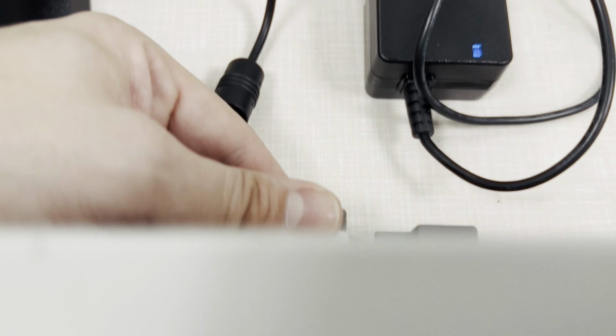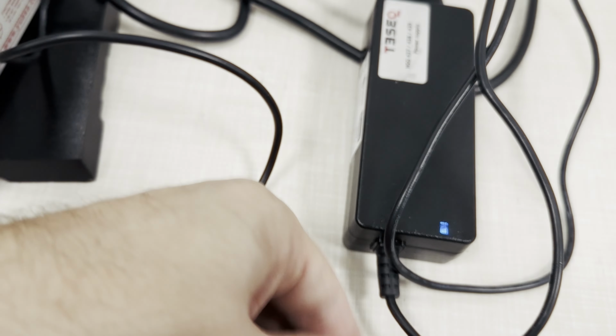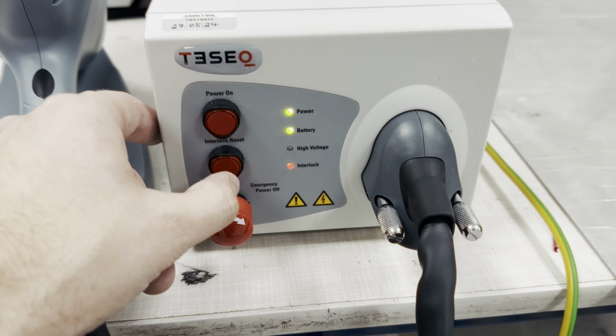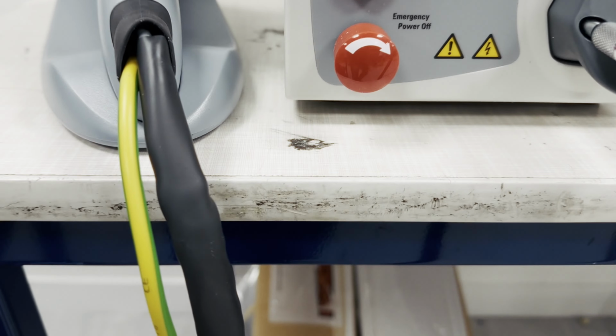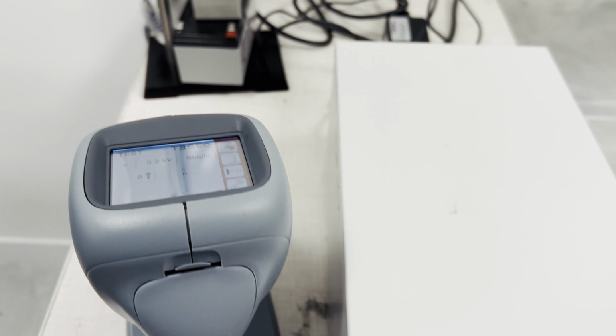So I have checked the earth connections, and they look good, so now I can switch on the equipment. When we turn on the test set, we'll see that it's been powered on, but we'll also see that the interlocks are now open, and it's very important with this one to make sure that these connectors are actually plugged in, otherwise it won't work. So that's something that I often forget about. Then once it's ready, you can click the interlock reset button, and now it can really begin.